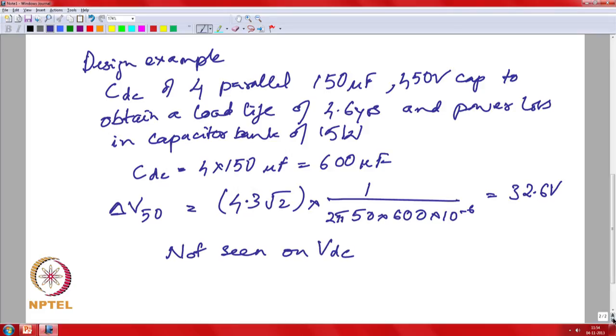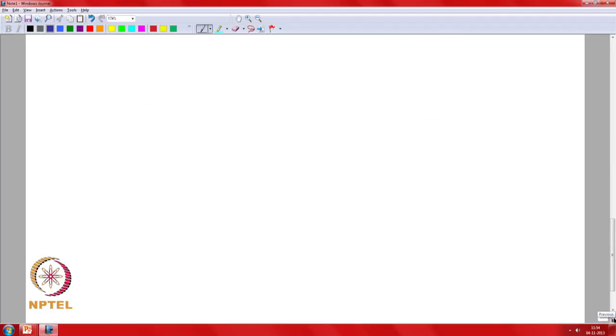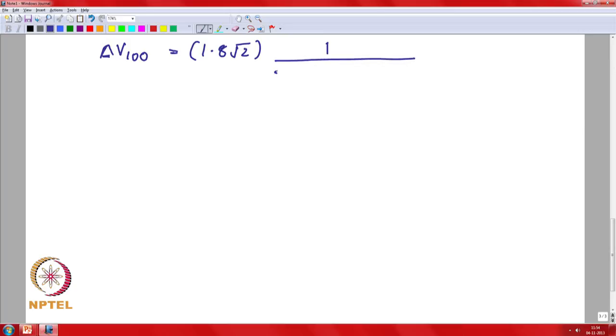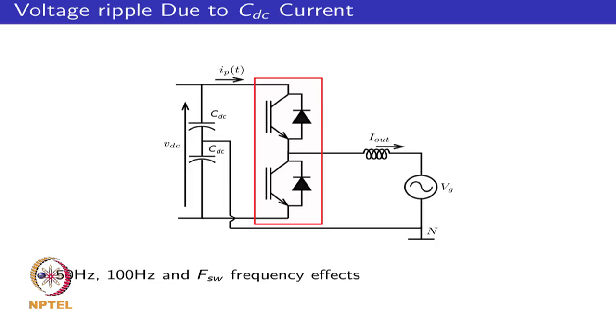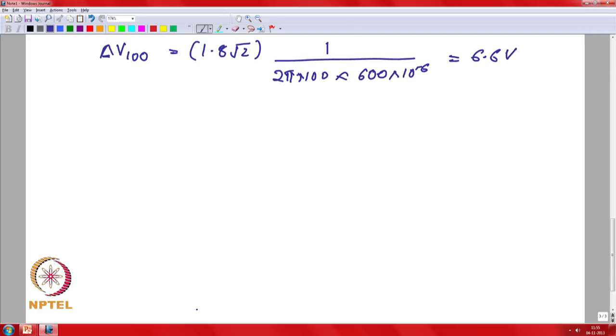Looking at the 100 Hz effect: we had 1.8 A flowing through the capacitor, times root 2 to get the peak. The impedance is 1/(2π × 100 × 600 µF), giving 6.6 volts per capacitor bank. Because this current flows as a differential-mode current through the bank, you have +6.6 V on top and +6.6 V on the bottom, so it adds up. It is seen as 13.2 V ripple on VDC.